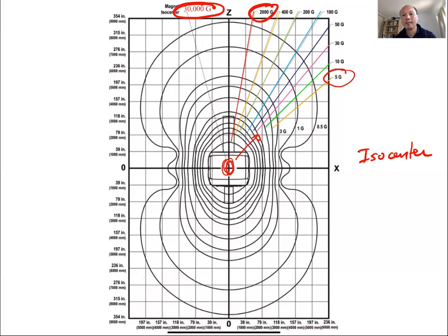And the reason for that is, although it's not clear what the actual limit is, there's been this rule for a long time where anyone with a pacemaker has to stay outside the 5 Gauss line. Now that might not be true for modern pacemakers, but certainly in the old days, if you walk through, as you can sort of see, this is a spatially varying magnetic field. And so if you walk through a spatially varying magnetic field, you're going to induce a time varying magnetic field, which is going to cause currents, which could cause your pacemaker to go haywire.